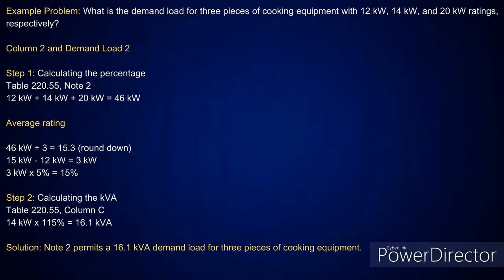Once I round down to 15 kW, I'm going to subtract what? The 12 kW, just like I did before. That's going to give me 3 kW. Take that at 5% for each additional kilowatt, that's going to give me 15%. Then if I go over and pick up 3 appliances and look at column C, it's going to tell you it's good at what? 14 kW. So I'll take the 14 kW at 100% of the load plus the 15% for each additional kilowatt, and that's going to give me 16.1 kVA or 16,100 VA for the 3 pieces of cooking equipment.